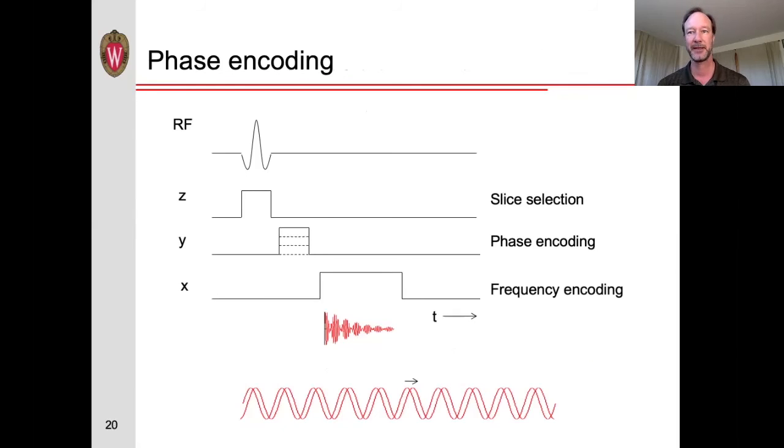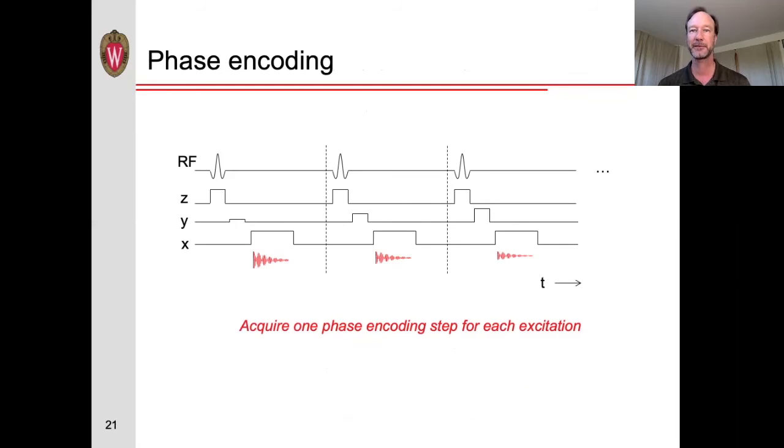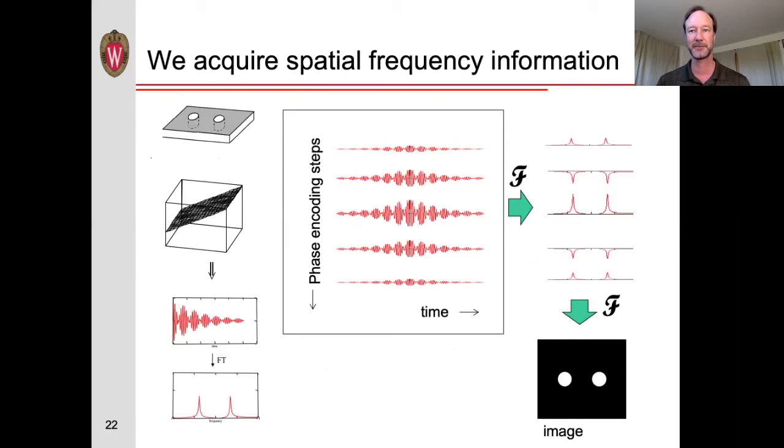However, a more commonly used technique is what is called phase encoding. Instead of applying a gradient during the excitation or during the acquisition, we can apply a gradient for a short time in between the two. This additional gradient shifts the phase of the signal being measured. We then have to repeat this procedure multiple times, each with a slightly different amplitude of the phase encoding gradient and use a set of these signals to form a 2D image. If we stack the set of these acquired signals, each with a different phase encoding gradient amplitude, then if we look at the frequencies in each of those signals in the x direction, we can get an image in the x direction, and similarly, if we look at the frequencies in the y direction across different phase encoding steps, we can get our image in the y direction. Now, this concept is often difficult to understand, at least it was for me when I was first learning about MRI, so let me break this down in a slightly different way.